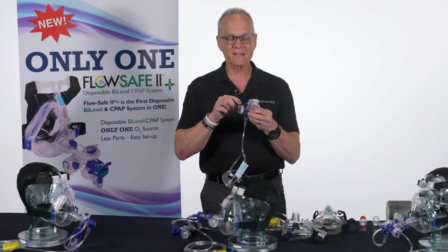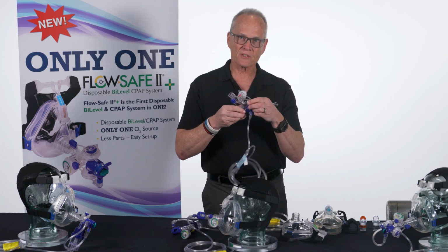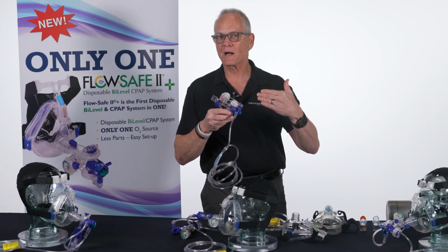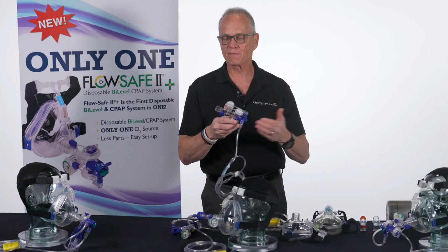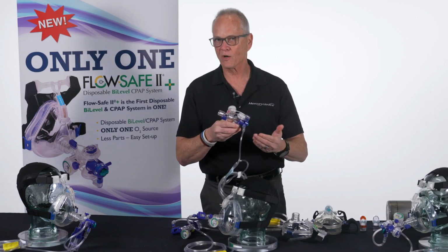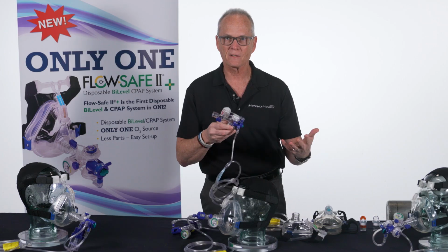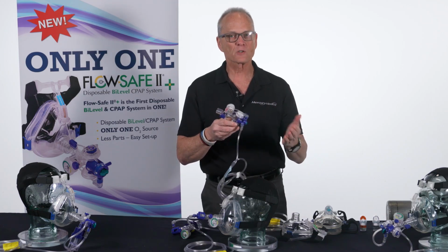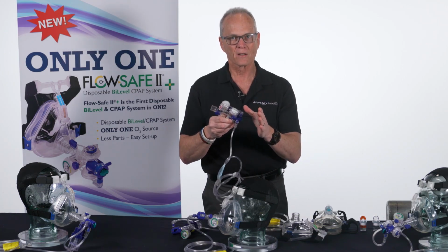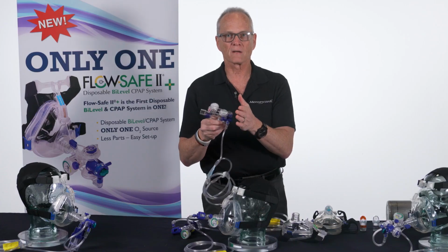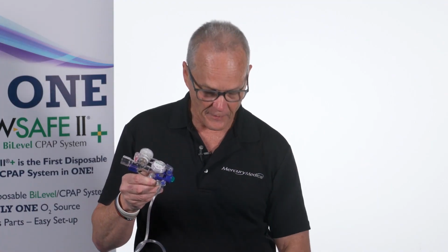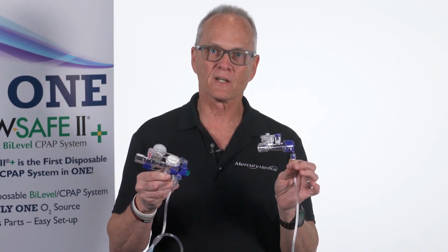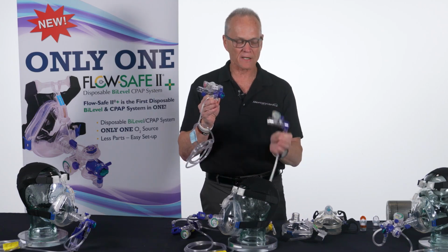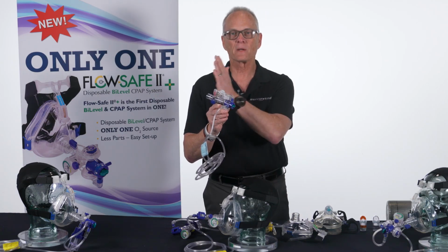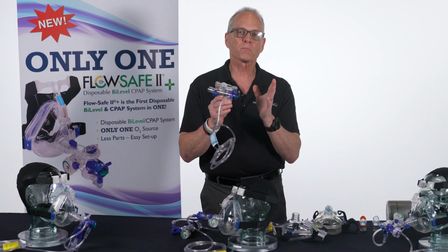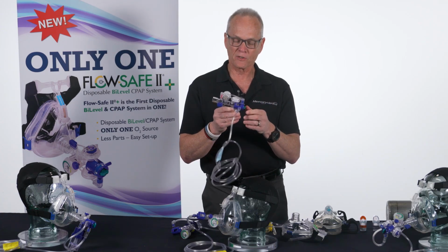Now, I'm not going to try to tell you that this is the same as a BiLevel ventilator. It doesn't have a backup rate. It doesn't have any alarms. There's no timed rate. It has none of that. So it's not replacing a $15,000 ventilator. But it does more than what a plain CPAP device does. It's that gap patient that goes between CPAP and being on a ventilator. That's the patient that we're looking at here to do that.